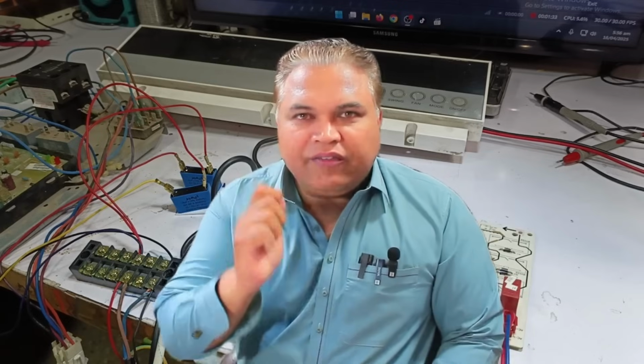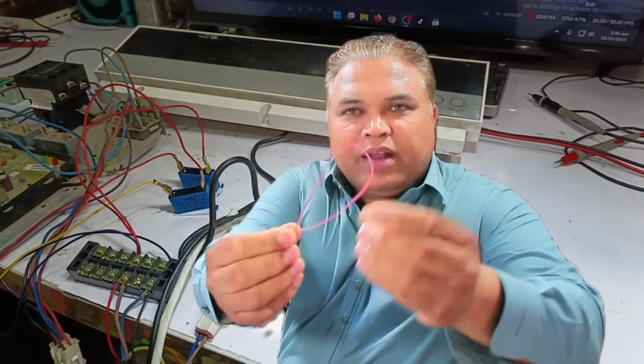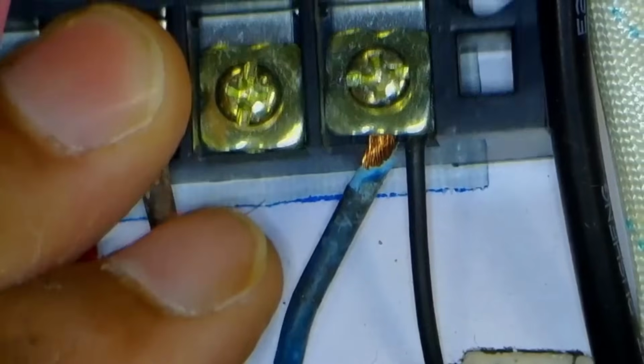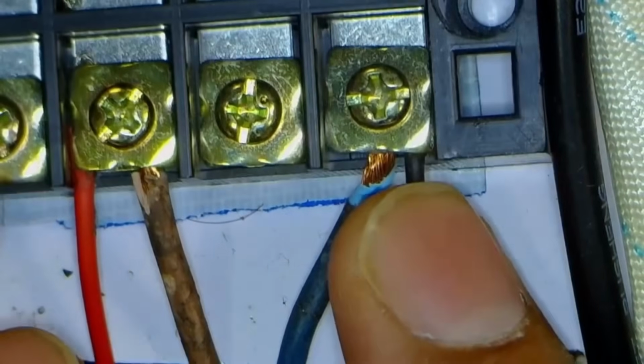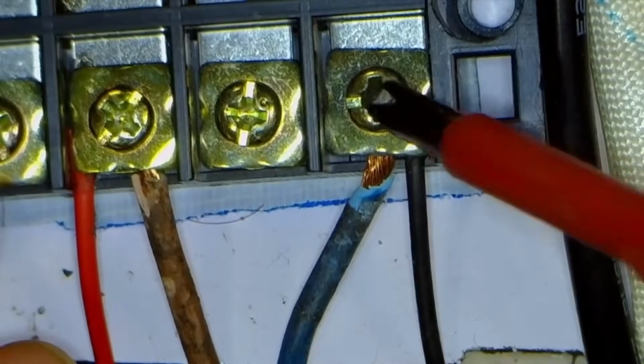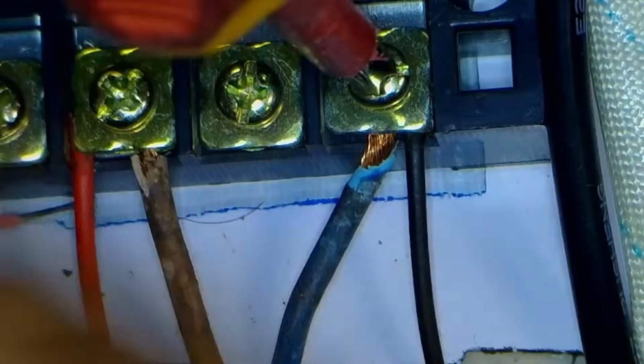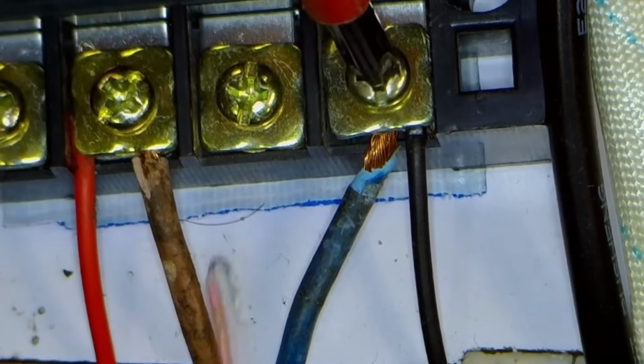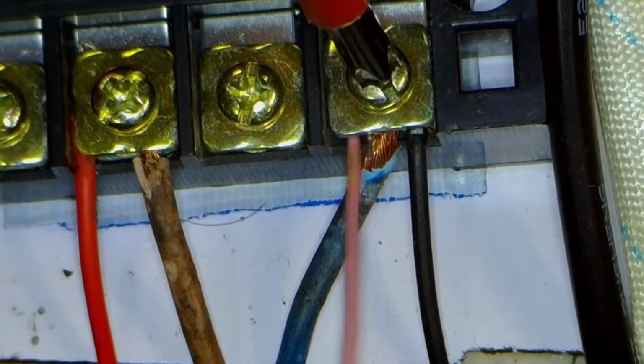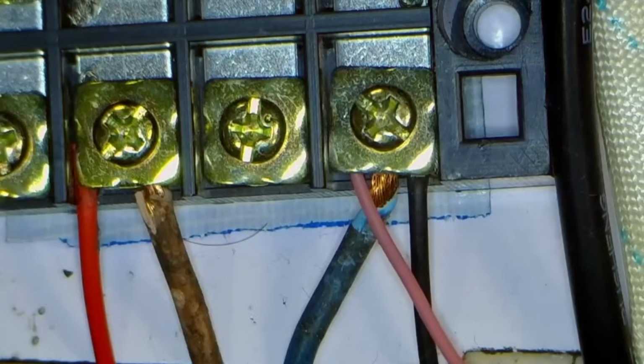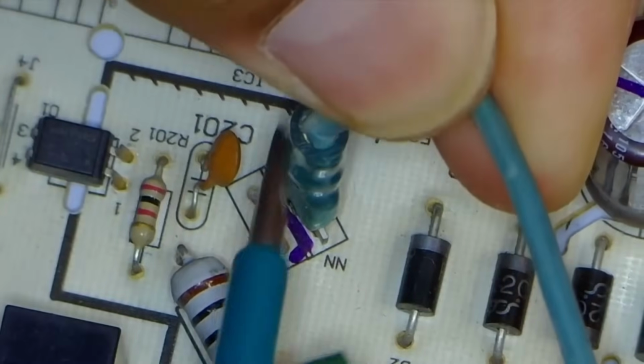Now we will perform another test, a simple but highly effective test, which will give us a better idea of where exactly the problem lies. For this test, we will take a wire and use it to perform the check. Here we have the main neutral wire from the single-phase supply that we already connected, and now we will attach this additional wire to it. All the other connections are already in place, so we will connect this extra wire alongside them, and it is now ready. What I will do next is disconnect the signal wire from the indoor unit so that we can perform this test properly. I have now removed the signal wire.